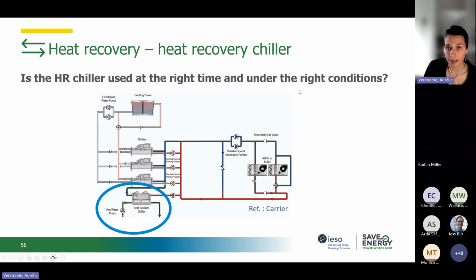Another heat recovery system that you can have in a chiller plant is the heat recovery chiller. Here you want to question whether the HR chiller is used at the right time and under the right conditions. You have to prioritize the heat recovery chiller when there are heating loads in the building. And you also want to optimize heating loop temperatures to benefit the most from the heat recovery chiller.